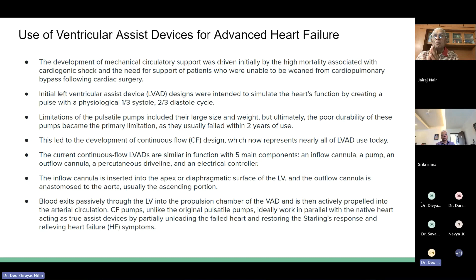Blood exits passively through the LV into the propulsion chamber of the VAD and is then actively propelled into the arterial circulation. Continuous flow pumps, unlike the original pulsatile system, ideally work in parallel with the native heart, acting as true assist devices by partially unloading the failing heart, restoring the Starling response, and relieving heart failure symptoms. There are two types of continuous flow pumps currently available for commercial use: axial and centrifugal design.